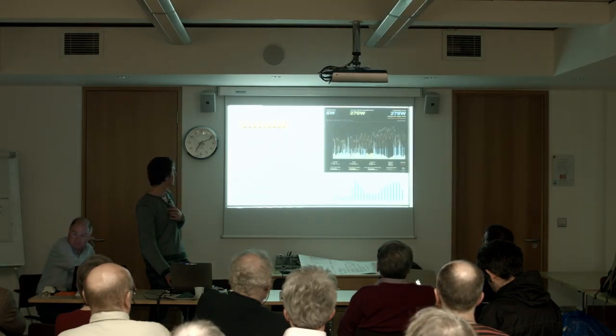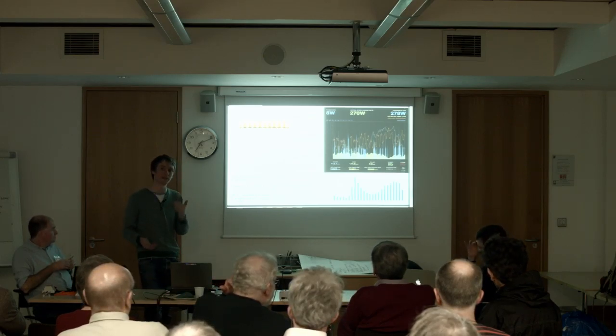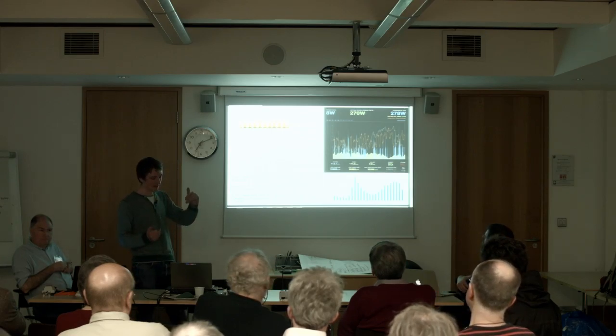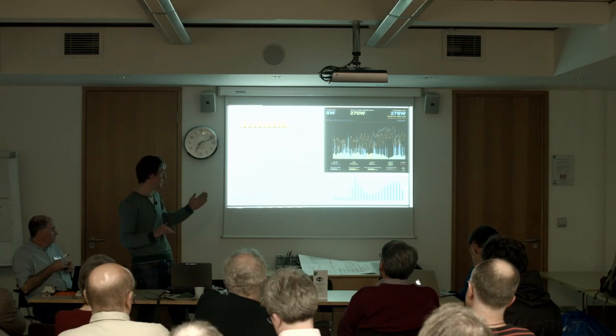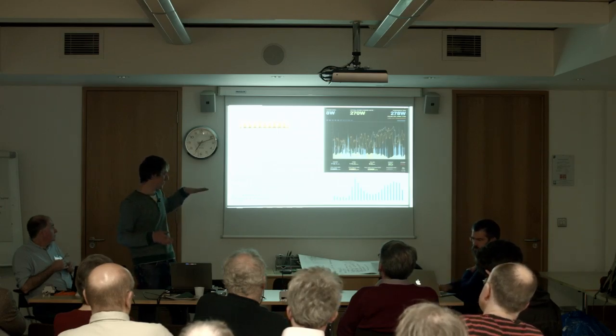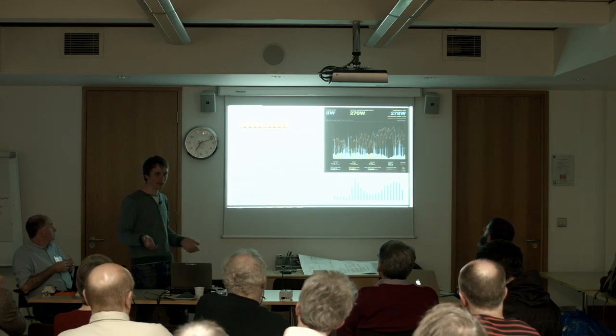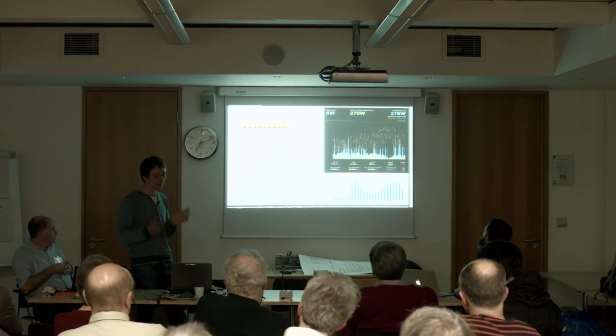These graphs of system properties and flow temperatures are all useful to understand how well the system's working. Perhaps one of the more interesting aspects is the matching between real-time data from grid CO2 intensity and real-time wind output — looking at the degree of matching between supply and the heat pump demand. I've recorded 35% supply-demand matching with this heat pump, which is not particularly high. The modelling suggests you should be able to achieve about 57%, but this is a good baseline for me to improve on over time.